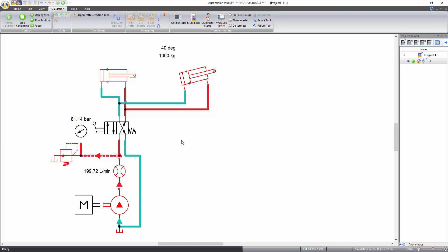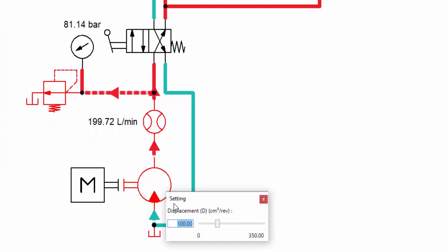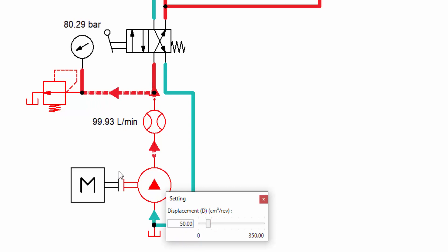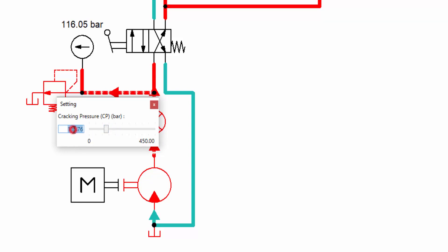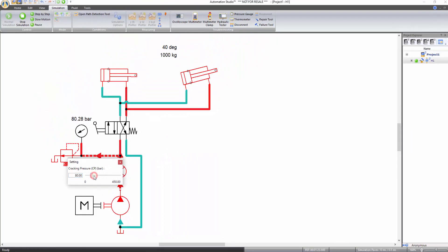You can also change parameters during simulation. For example, moving your mouse over the pressure relief valve or the pump will change the cursor to a hand. Left click to modify its setting and the effect of these changes can be seen in real time. If you reduce the displacement of the pump to half — that is, 50 — you can observe that the flow in the circuit decreases by that factor. Similarly, if you modify the cracking pressure of the relief valve, you can observe the change in pressure readings of the pressure gauge. Restore the default values and stop simulation.